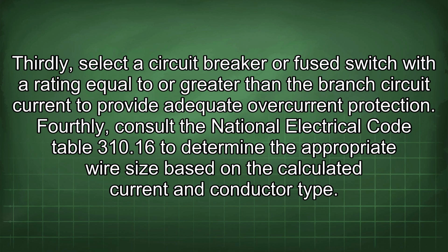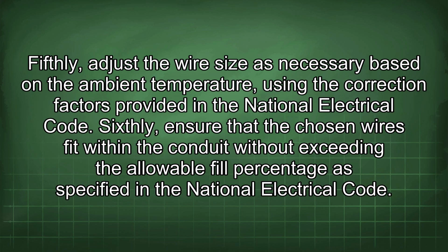Fourthly, consult the National Electrical Code Table 310.16 to determine the appropriate wire size based on the calculated current and conductor type. Fifthly, adjust the wire size as necessary based on the ambient temperature, using the correction factors provided in the National Electrical Code. Sixthly, ensure that the chosen wires fit within the conduit without exceeding the allowable fill percentage as specified in the National Electrical Code.